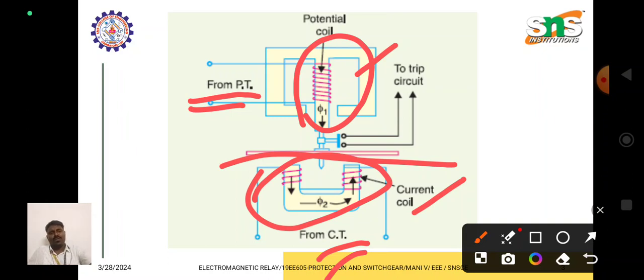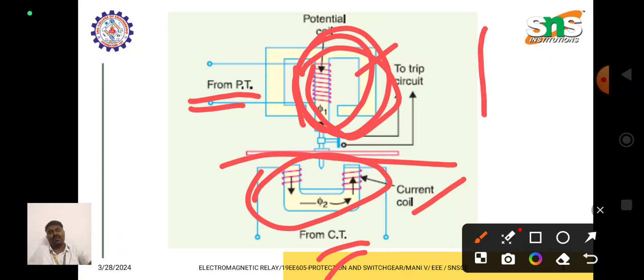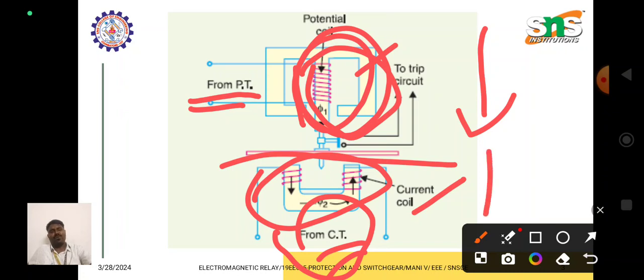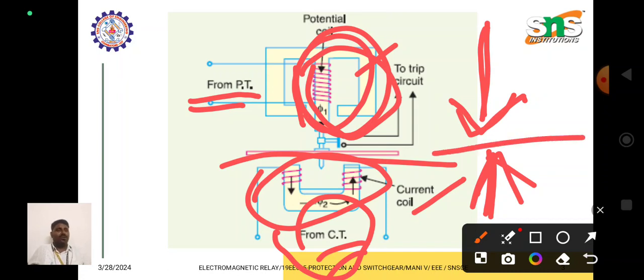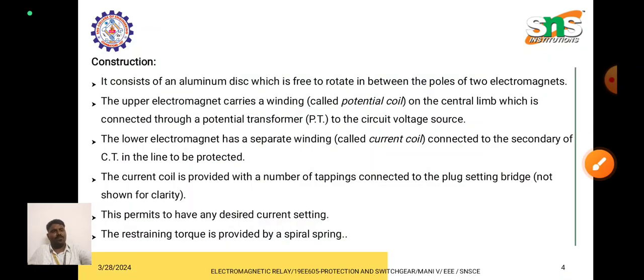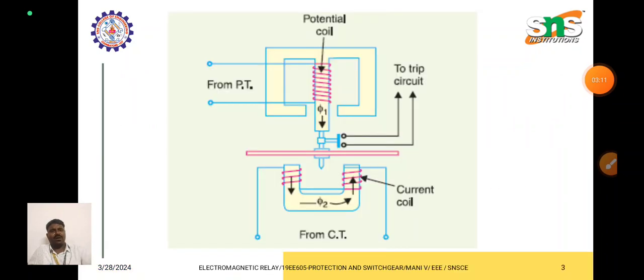Here the voltage is applied to the potential coil. The potential coil gets energized and produces electromagnetic flux, which moves downwards. Similarly, from the current transformer, the current is delivered to the current coil. The current coil gets energized and produces some amount of flux, which moves upwards. So one flux comes from upper to lower, and the other from lower to upper. The two fluxes interact on the aluminum disc, and because of this interaction, a torque is induced in the aluminum disc, so the disc rotates.